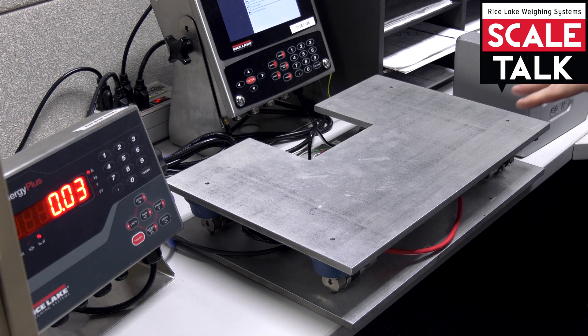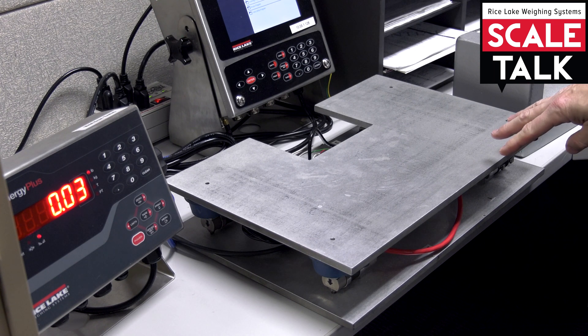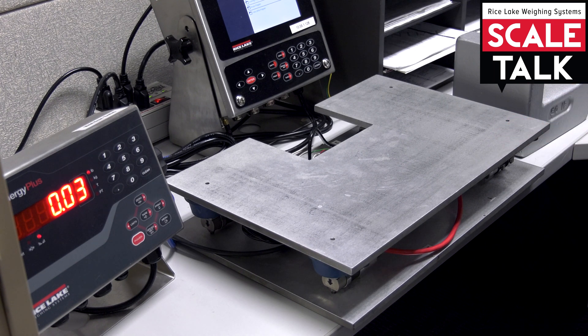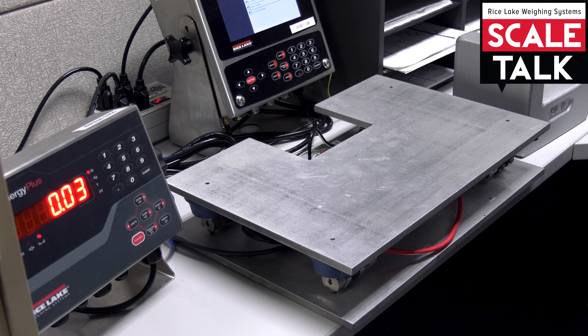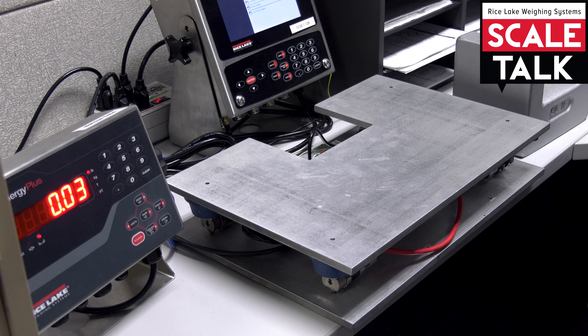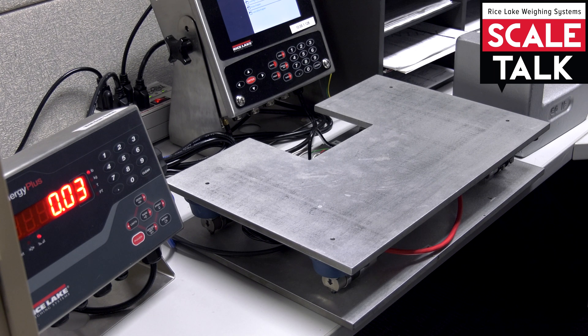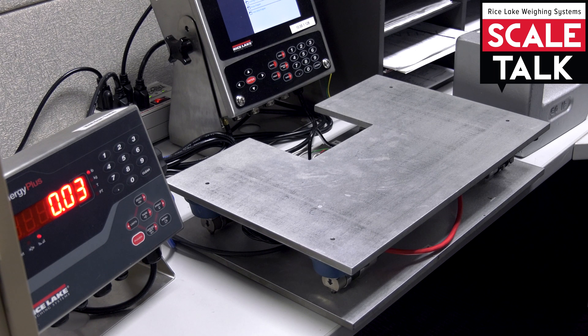In this particular case, I have a 50 pound scale base here and Handbook 44 would recommend that I use a full 50 pounds to calibrate the scale.